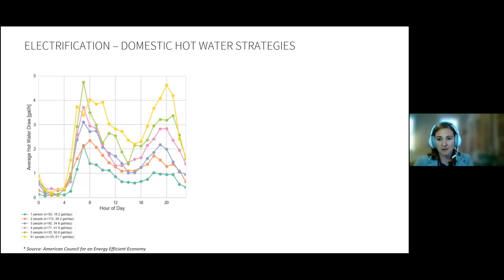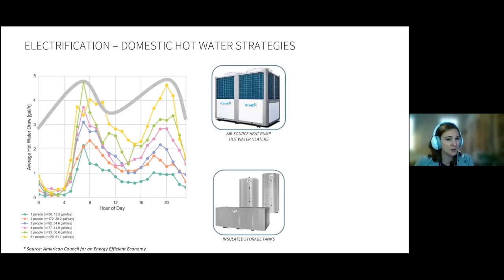So most domestic hot water systems work in real time to accommodate those peak loads. For example, electric resistance domestic hot water heating can respond almost instantaneously at the time of that peak demand. But heat pumps, they're far more efficient than those electric resistance ones, but they work slowly over time and they don't really respond well to those peak loads instantaneously. So as Joe mentioned previously, these systems do require hot water storage, a capacity big enough to accommodate that peak load. The gray line here that we've added to this chart represents the amount of heat in those storage tanks. So after that first peak load, the hot water is drawn down pretty quickly.